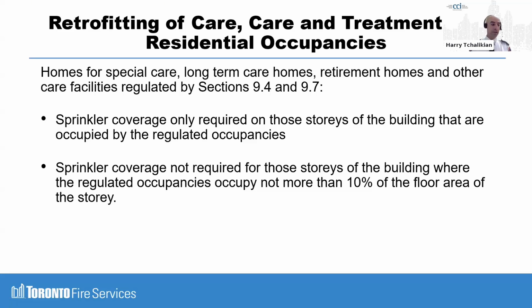So when the 2015 Fire Code and Section 9.7 first came out, the requirement was, if you had a residential apartment building, but all of a sudden you've inadvertently or on purpose knowingly veered into a B3 major occupancy, such that now you have residents that need care for daily living, personal services workers, and they need assistance to evacuate, in those cases you automatically needed a fully sprinklered building. So this is a relaxation.